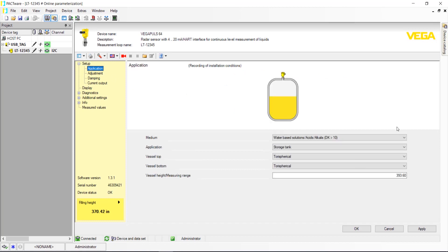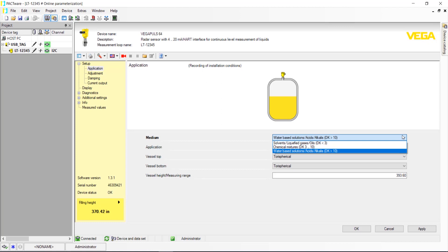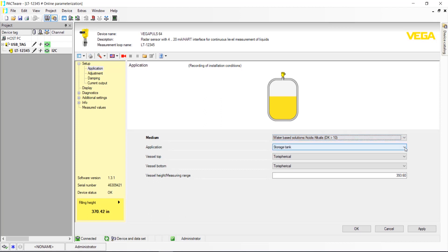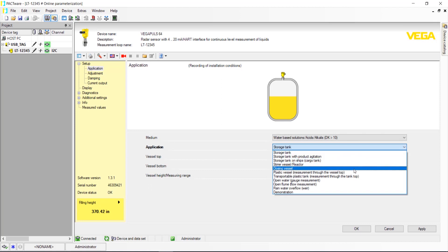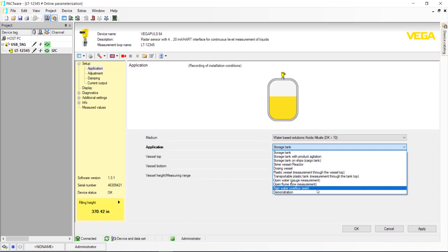Medium tells the sensor what's being measured: a solvent, a chemical mixture, or a water-based liquid. This tells the sensor electronics how big of a return signal it can expect. Application tells the sensor electronics what kind of surface the radar is measuring and how quickly the level will be changing.